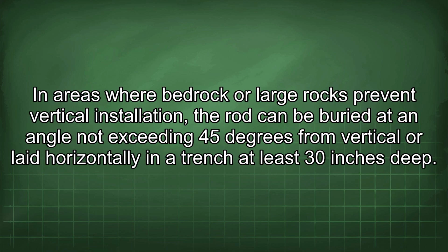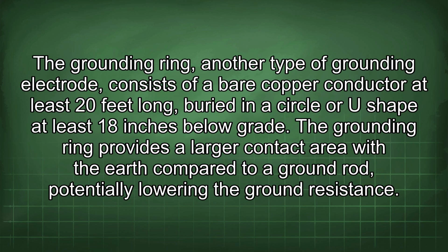In areas where bedrock or large rocks prevent vertical installation, the rod can be buried at an angle not exceeding 45 degrees from vertical or laid horizontally in a trench at least 30 inches deep. The grounding ring, another type of grounding electrode, consists of a bare copper conductor at least 20 feet long, buried in a circle or U-shape at least 18 inches below grade. The grounding ring provides a larger contact area with the earth compared to a ground rod, potentially lowering the ground resistance.